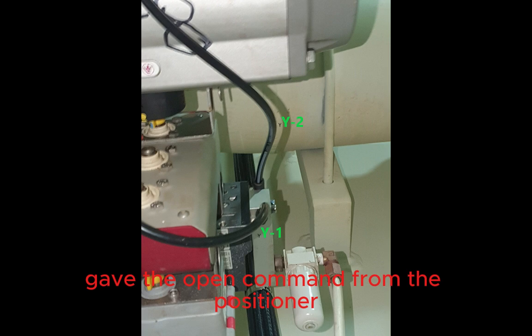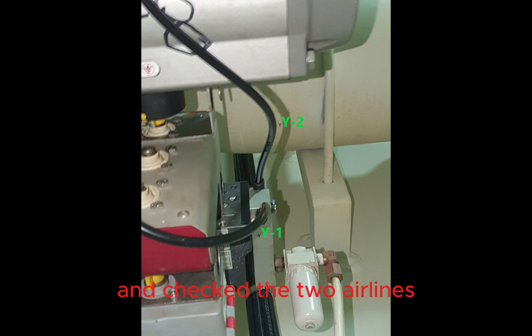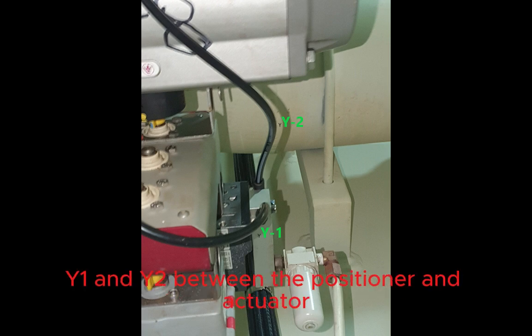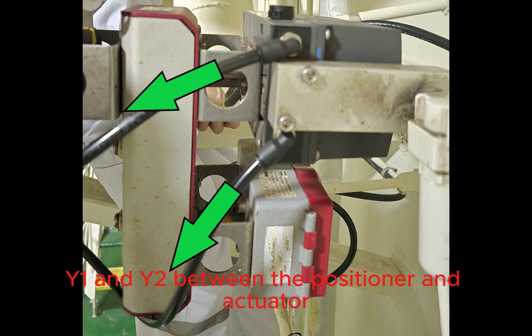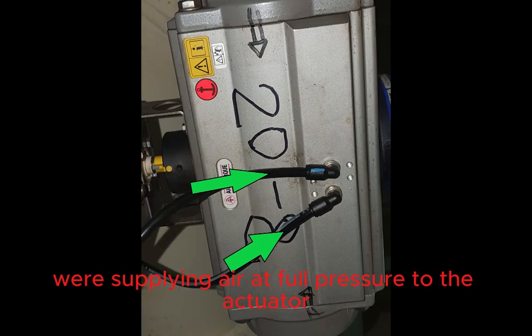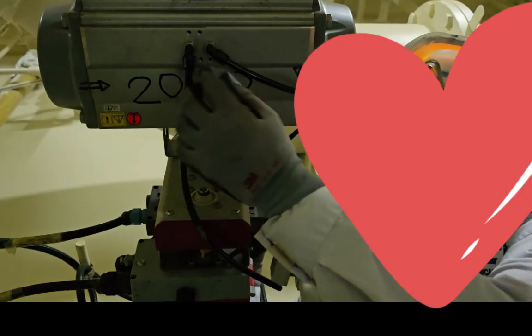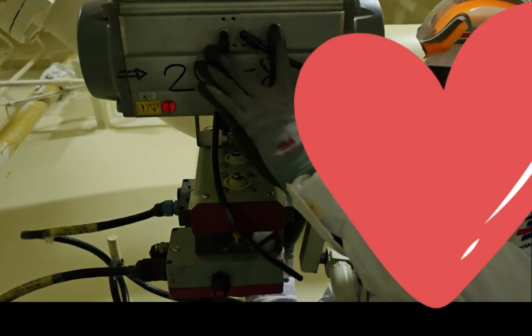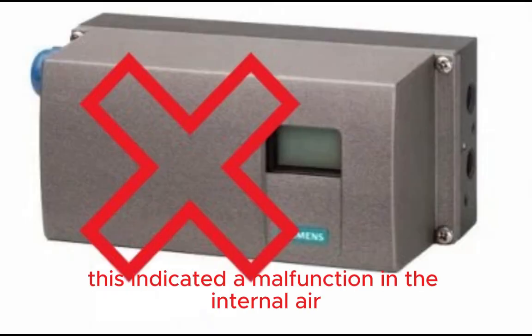I gave the open command from the positioner and checked the two airlines Y1 and Y2 between the positioner and actuator. I found that both lines were supplying air at full pressure to the actuator, instead of one supplying and the other venting. This indicated a malfunction in the internal air control of the positioner.